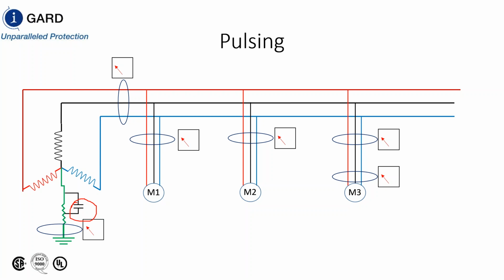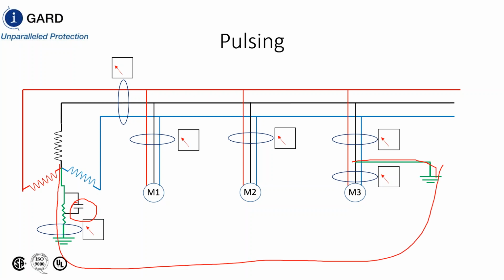And we do that cyclically. For example, 1 second that contactor is closed, another second that contactor is open. So when we turn on the pulsing, what we're doing is we're opening and closing that contactor. When we close it, we have 27 ohms. When we open it, we have 55 ohms. That means the fault signature changes. So if we have a ground fault here, the only place for that fault current to go back is through this resistor.